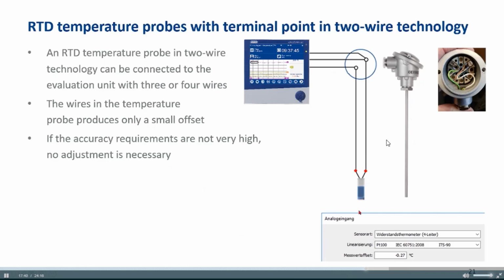And to make it clear, I said here, okay, offset minus 0.27 centigrade. Maybe I found out through a reference measurement, whatever, that the offset caused by this line here is 0.27 centigrade. And here I make my offset correction. Now I hope you understand. And to make this 100% clear for you, I have a photo of this connection from this probe. So you see here I work with 3 wires. The probe is in 2-wire technology. I give 2 wires to one terminal, and I give this other wire to the other terminal. And this solves your problem in general. And if you want to make it as good as possible, use 4 wires.